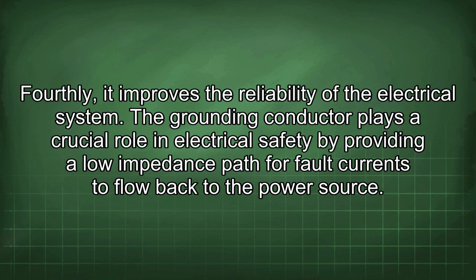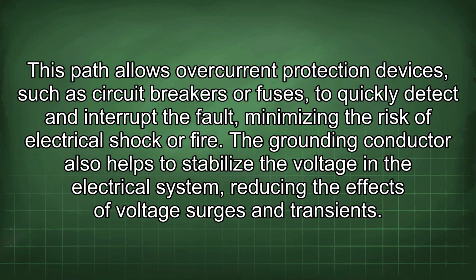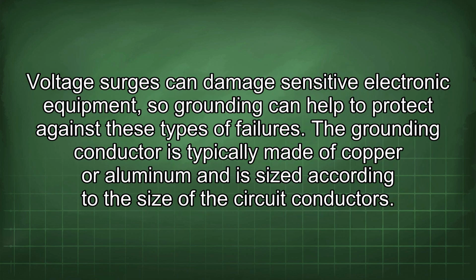The grounding conductor plays a crucial role in electrical safety by providing a low impedance path for fault currents to flow back to the power source. This path allows overcurrent protection devices, such as circuit breakers or fuses, to quickly detect and interrupt the fault, minimizing the risk of electrical shock or fire. The grounding conductor also helps to stabilize the voltage in the electrical system, reducing the effects of voltage surges and transients. Voltage surges can damage sensitive electronic equipment, so grounding can help to protect against these types of failures.